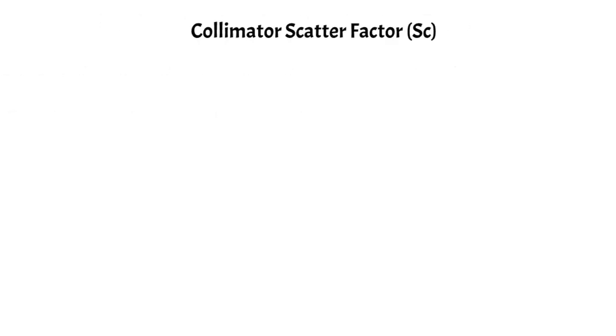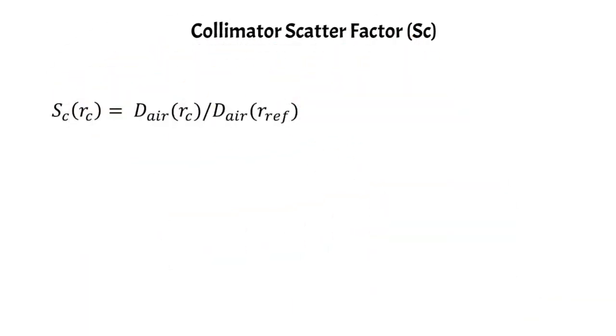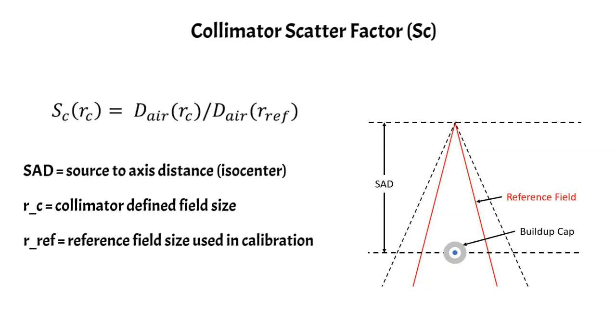Let's start with the collimator scatter factor, or Sc. The definition of the collimator scatter factor is a ratio of doses measured in air — one with the field size equal to R sub C, and the other equal to the reference field size R sub ref. The collimator scatter factor is always measured at SAD, and you measure it with a small buildup cap to mitigate the effects of the buildup region. The reference field size is shown in red, and the collimated field size is the black dotted lines. SAD is the source-to-axis distance, R sub C is the collimator-defined field size, and R sub ref is the field size used during calibration of the linear accelerator.